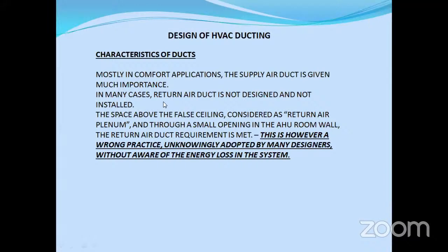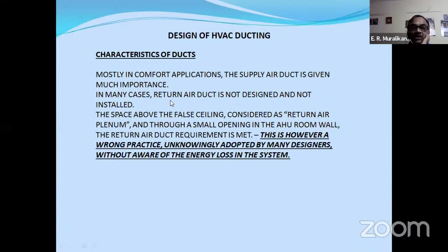I was coming to the return duct. In many cases, the return duct is not designed and not installed. The reason being, the space above the false ceiling is considered as return air plenum, and through a small opening in the room wall, the return air duct requirement is met. This is, however, a wrong practice unknowingly adopted by many designers without being aware of the energy loss in the system. I will brief you when we go to the other slides. In many cases, architects say they don't want the return duct as a cost saving, but it has a very large impact on so many factors. I'll explain in the coming pages.